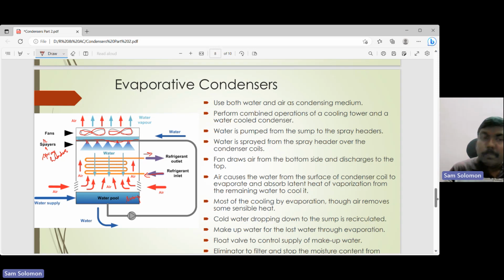As it carries them away, it's like the principle when you take a bath and stand under a fan, and you feel cold. Why do you feel cold? The air that passes over your body removes the heat from that body. In the meantime, that heat removal converts the water droplets present on your body into vapor form. A similar situation arises here. The air carries away the water, so the latent heat of vaporization is removed from the surface of the condenser coil. That converts your refrigerant vapor into refrigerant liquid.